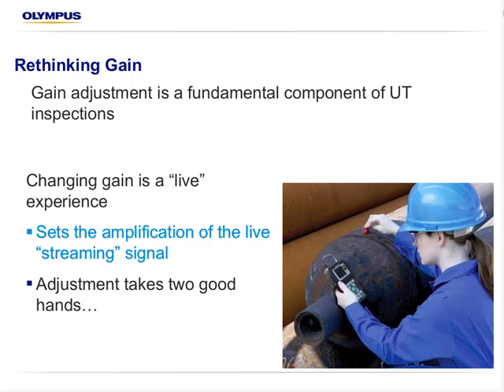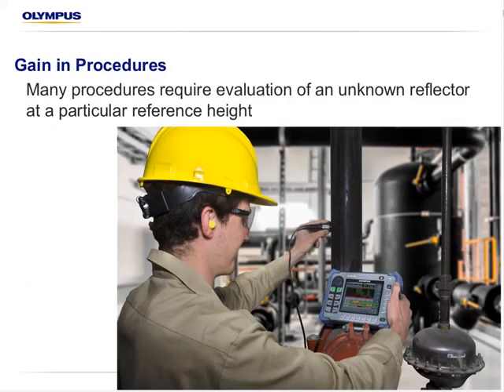So as in the picture that we see here, one hand is going to be on the instrument, whether you're holding it or whether you're just making adjustments while it's on a bench top to that gain. The other hand really needs to be holding the transducer in a static position. And really the important reason for this is that in most procedures, it's not enough to simply peak up the signal to find that static position and find where the echo height is at its highest. But in order to compare it to anything, we really need to amplify or to attenuate potentially that signal so that it's at a reference height.